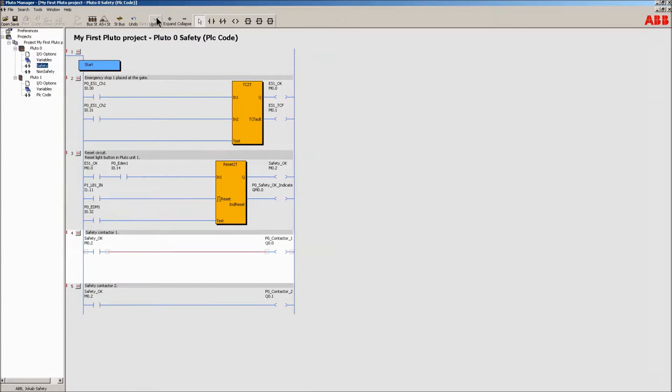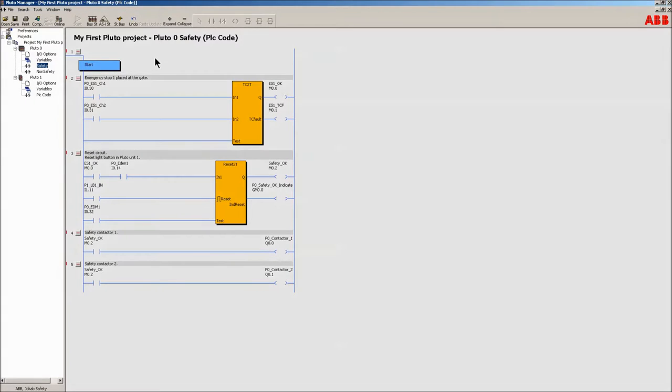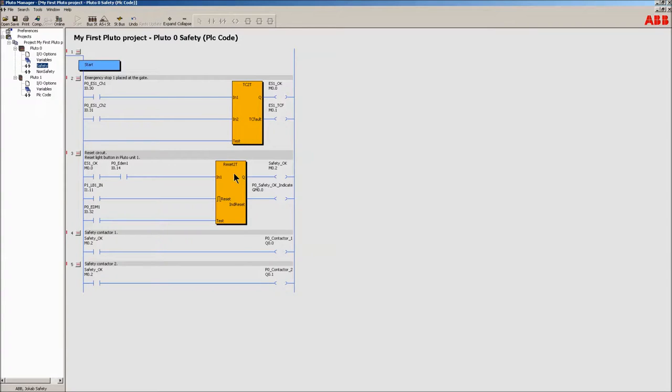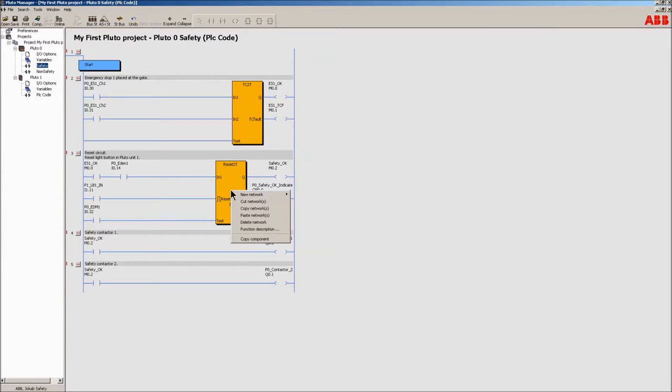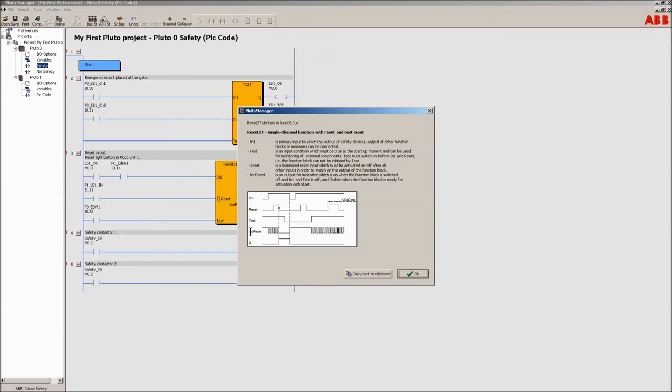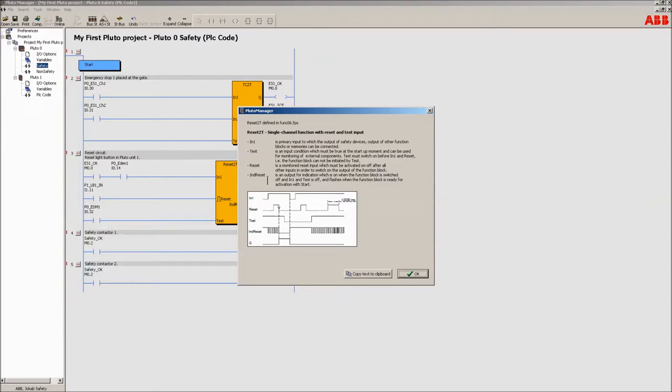Remember the light button in the other Pluto unit, unit 1? The reset2t block works so that the indicate reset output is steady high when it's not possible to reset the block. The output will flash if it's possible to perform a reset but a reset hasn't been called for. When the block is reset and the safe state is achieved, the output will be set to off.